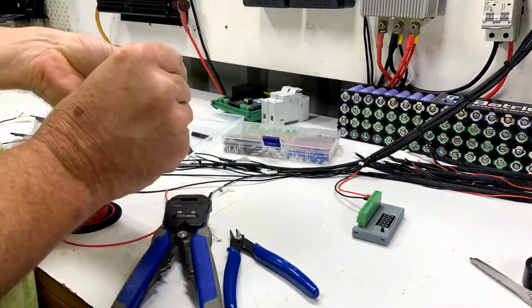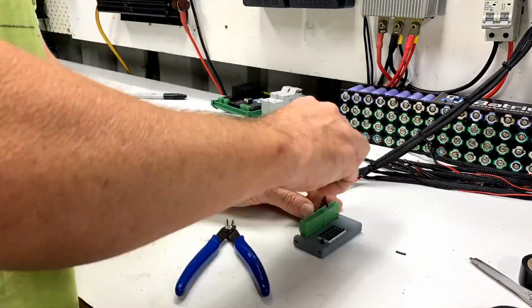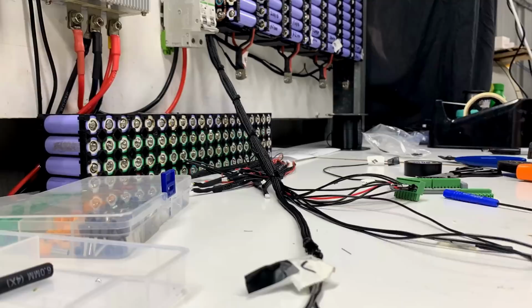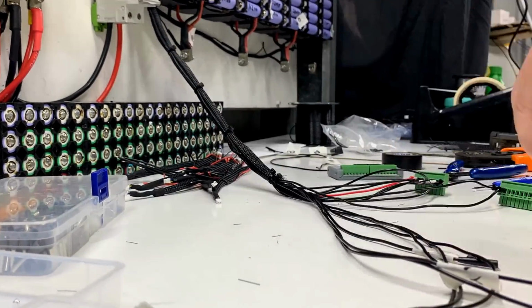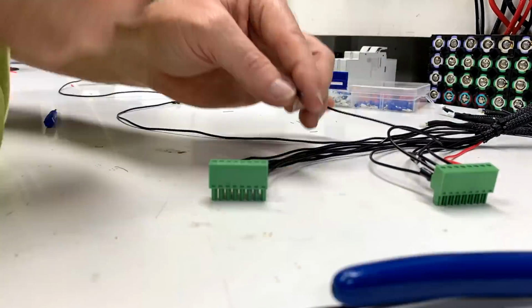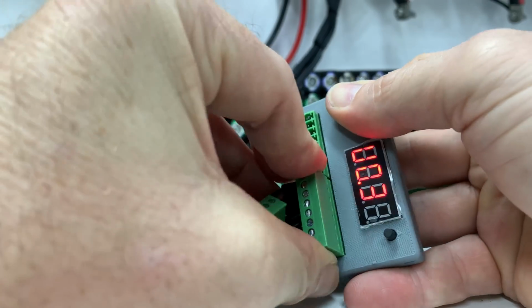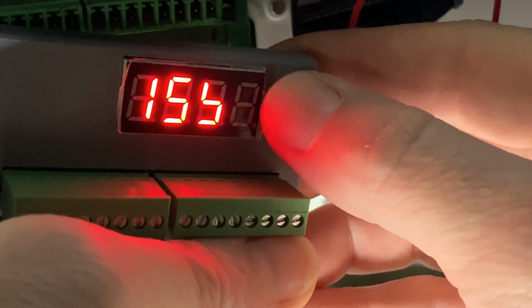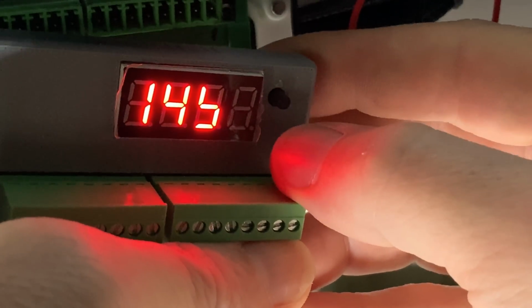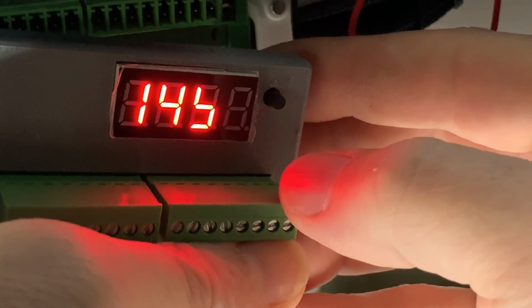Cables were run down the left hand side of the battery to the Watchmon Plus. The black ferrules I initially connected were too wide, but I confirmed the correct cable layout with the Testmon. Changing the Testmon into 14S mode, I was able to confirm all cables were correctly attached to the battery.